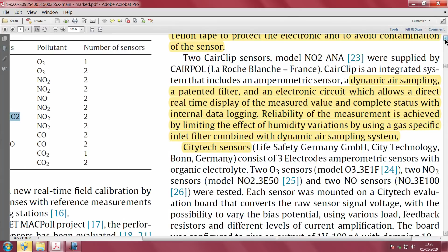Another important point is that whenever you do system design, you have to ensure that you avoid contamination of the sensor. Sensors measuring gases should not become contaminated and sluggish, so they must be kept clean when making a measurement. They put some Teflon tape to protect the electronics and avoid contamination of these sensors.